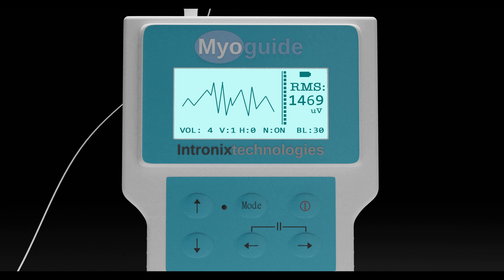Audio of the EMG signal can be heard through the built-in speaker. The audio volume, amplitude of the waveforms, and display speed can be adjusted using the arrows. The notch filter status and battery power level is also displayed here.